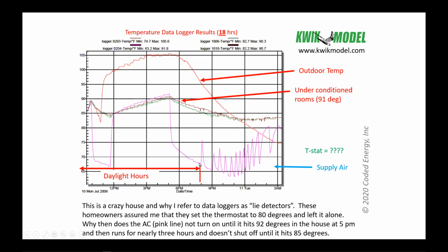So that's another thing that people don't realize: it takes a while for an air conditioner to run and reach its optimal performance, its optimal capacity and its optimal efficiency. It takes a while. Well, that's like 2 whole hours. Wow. That's 3 hours there. And it probably could have dropped even farther. Yeah. Wow. So if your system is shutting off every 30 minutes, it's never running in this high performance mode down here. I didn't realize that it took that long. I didn't realize that it kept incrementally getting cooler over that length of time.